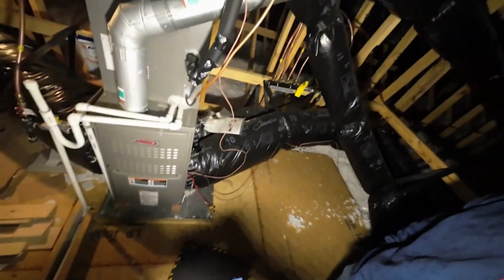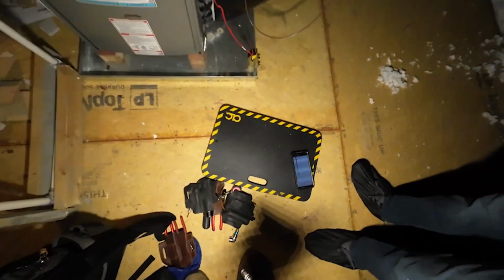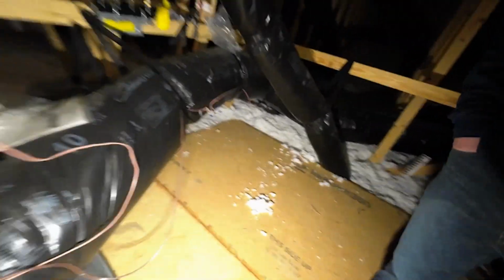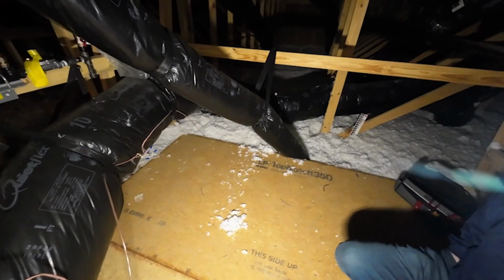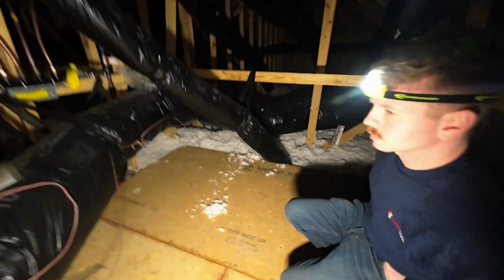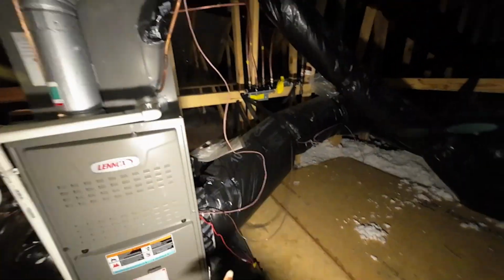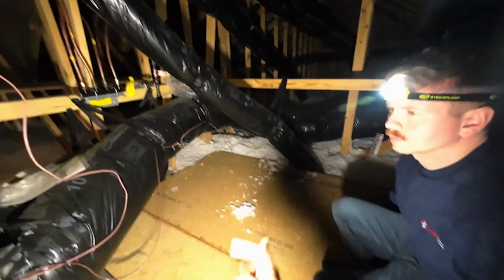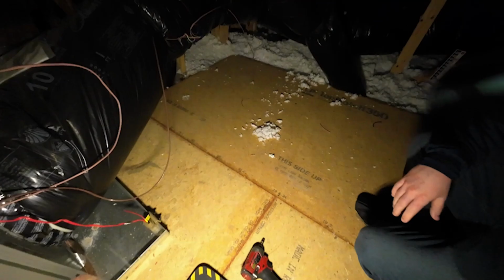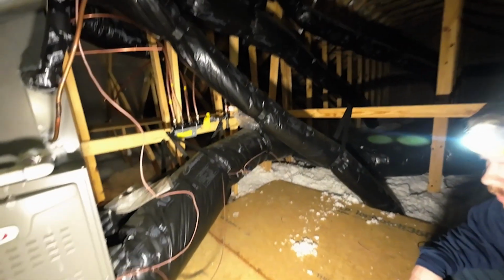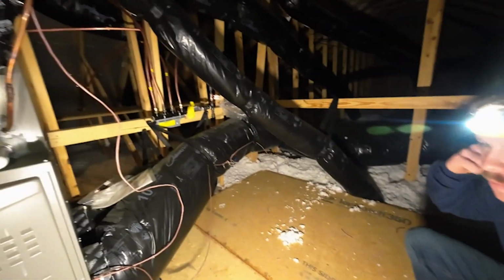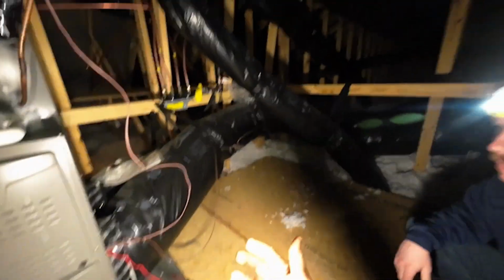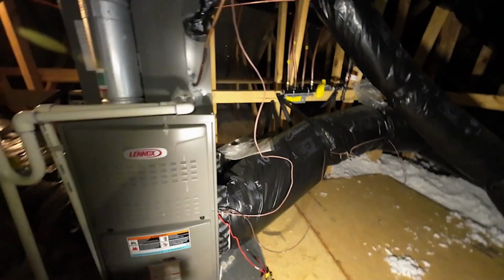Remember I told you how you can check most of the stuff with the system still running? So that's one, right? Now we'll figure out, what are we working on, upstairs or downstairs? The quick way to know that is just see how these returns terminate. This is what they call a return run, meaning this is where the air gets pulled back. It's returning the air to the unit. That's why it's called return. So you remember where we saw the filter, where I asked them how long it's been since you replaced that filter? Yep. That's the return register. That's why the filter's there, because it's filtering the air as it's being pulled back into the system.